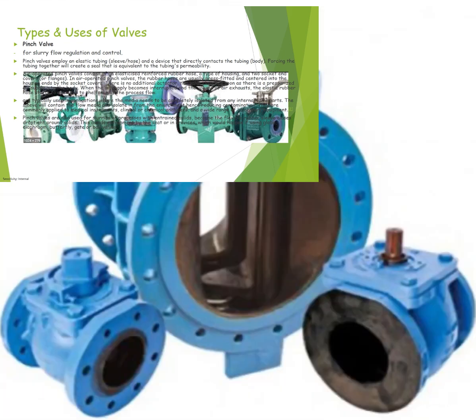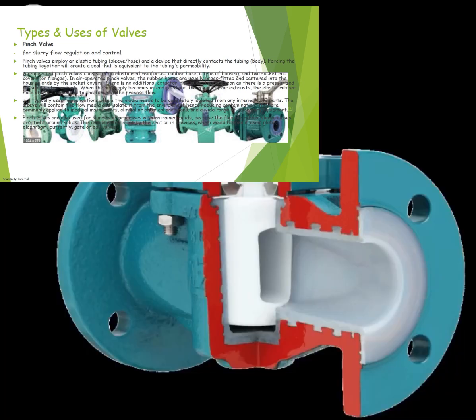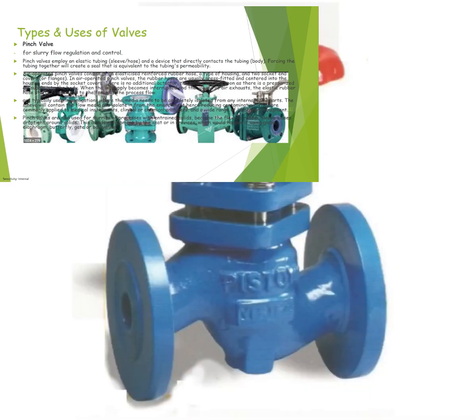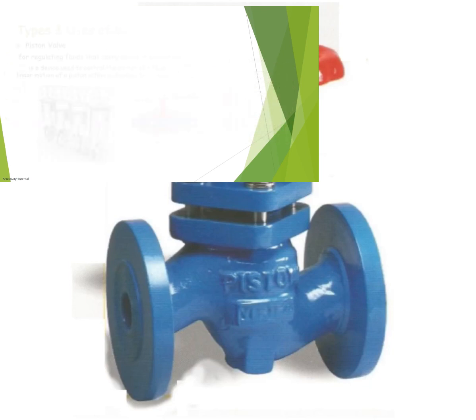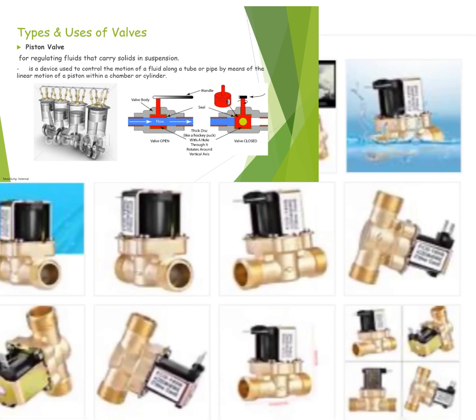An air-operated pinch valve consists of an elasticized range of reinforced rubber hose, a type of housing, and two socket end covers. In an air-operated pinch valve, the rubber hoses are press-fitted and centered into the housing ends by the socket covers. There is no additional actuator; the valve closes as soon as there is a pressurized air supply in the body. When the air supply is interrupted and the volume of air exhausts, the elastic rubber hose starts to open due to the forces of the process flow.